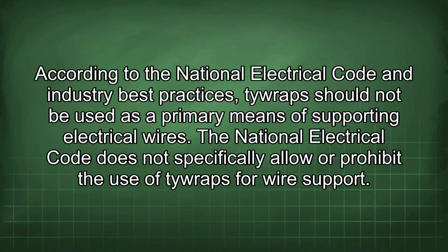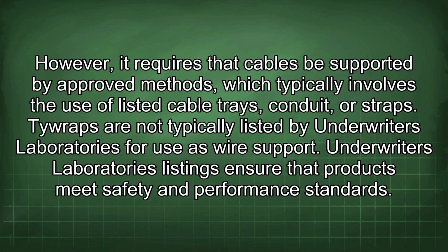According to the National Electrical Code and industry best practices, Tywraps should not be used as a primary means of supporting electrical wires. The National Electrical Code does not specifically allow or prohibit the use of Tywraps for wire support. However, it requires that cables be supported by approved methods, which typically involves the use of listed cable trays, conduit, or straps. Tywraps are not typically listed by Underwriters Laboratories for use as wire support. Underwriters Laboratories listings ensure that products meet safety and performance standards.